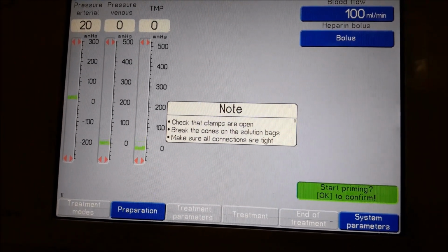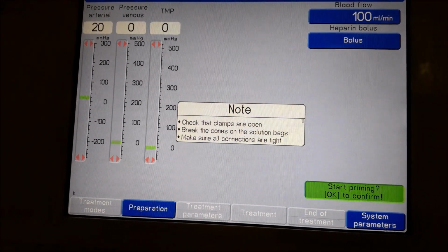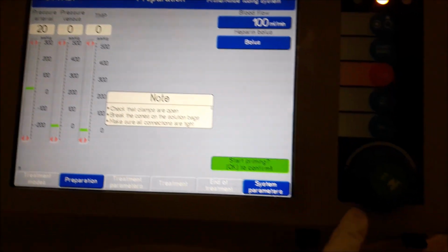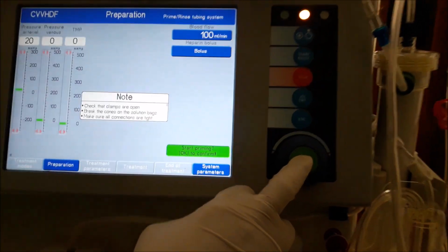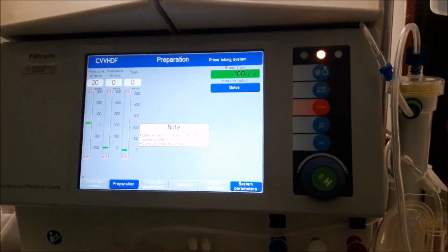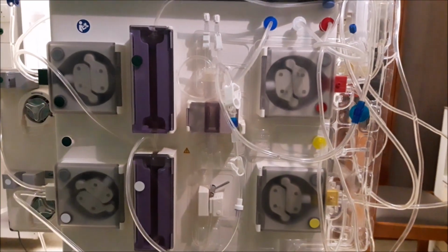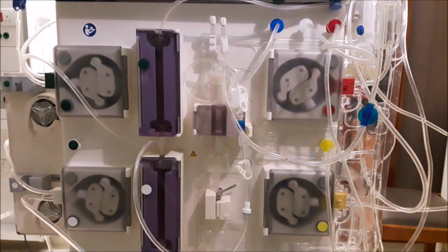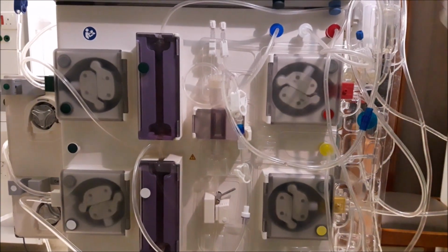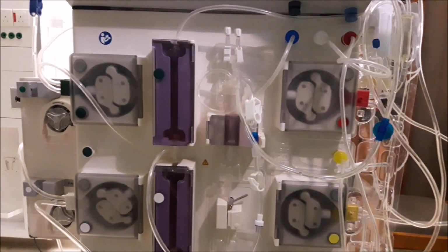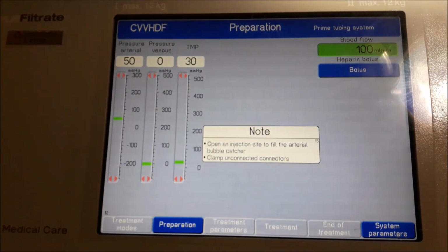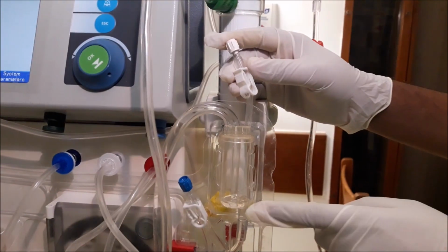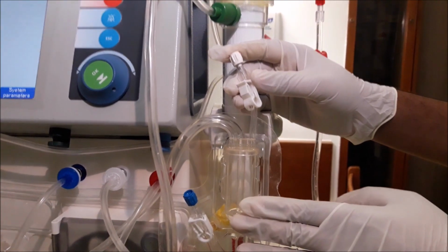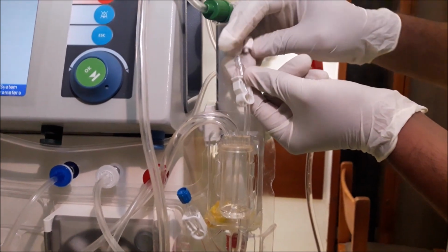Before priming, the third point is make sure all the connections are tight. Now press OK to start priming. Now the machine is giving the note: open an injection site to fill the arterial bubble catcher. This is the arterial chamber. We have to fill this chamber by opening the cap.